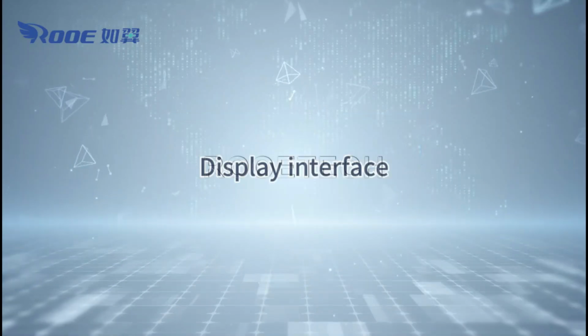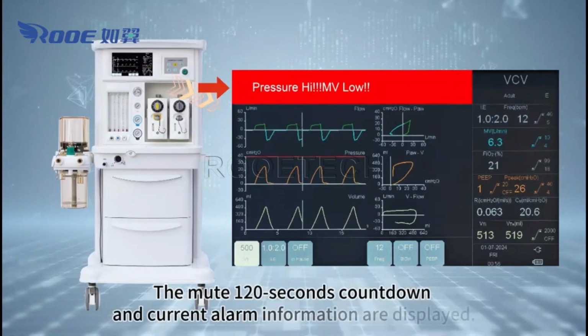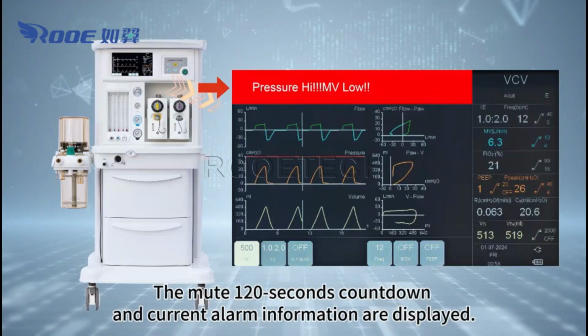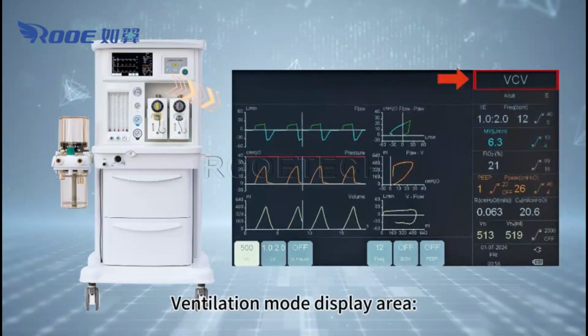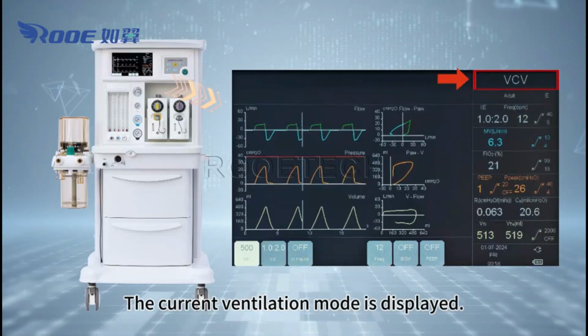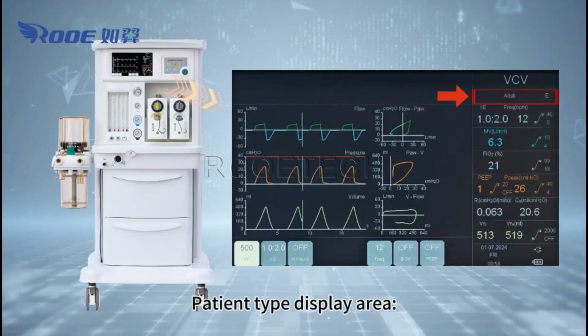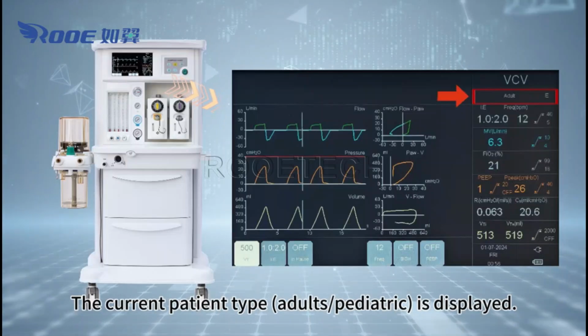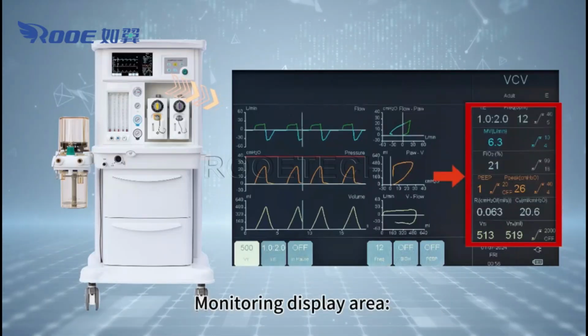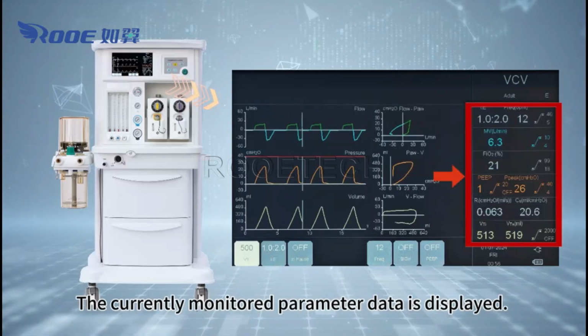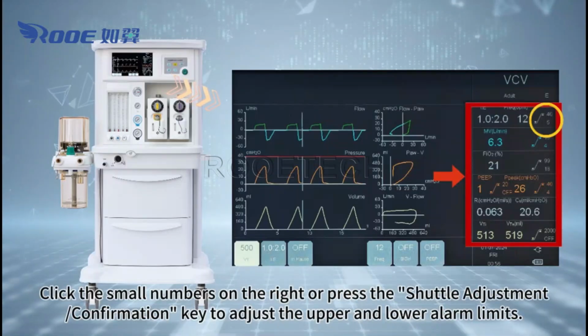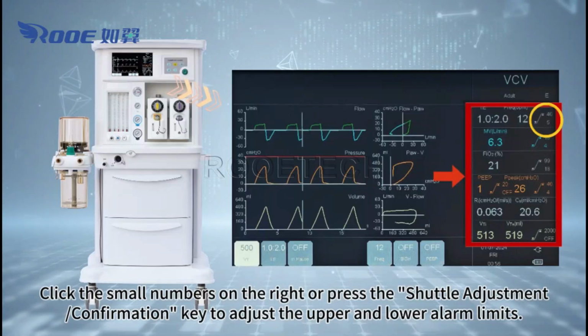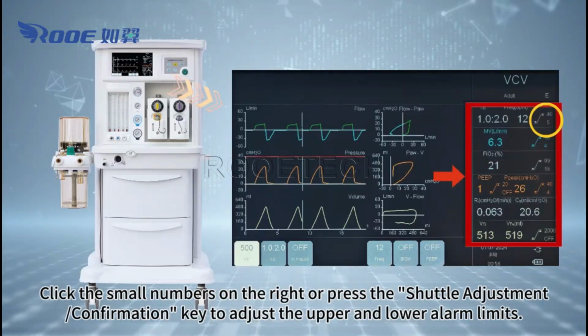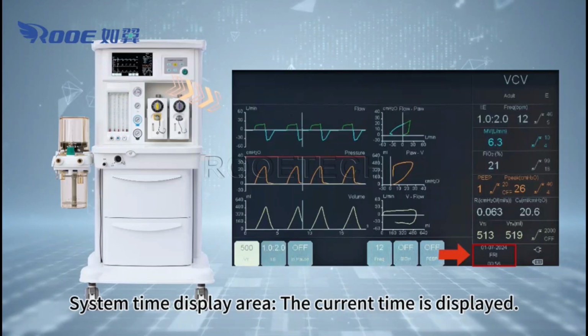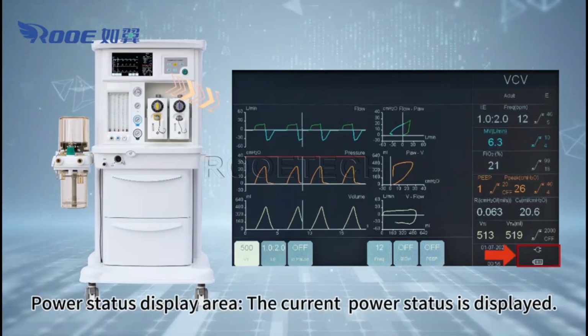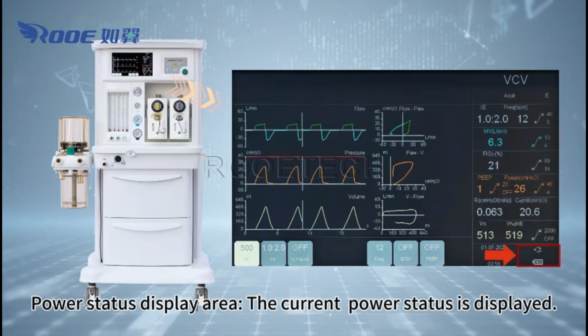Display interface. Alarm information display area, the mute 120 seconds countdown and current alarm information are displayed. Ventilation mode display area, the current ventilation mode is displayed. Patient type display area, the current patient type, adult/pediatric, is displayed. Monitoring display area, the currently monitored parameter data is displayed. Click the small numbers on the right or press the shuttle adjustment/confirmation key to adjust the upper and lower alarm limits. System time display area, the current time is displayed.